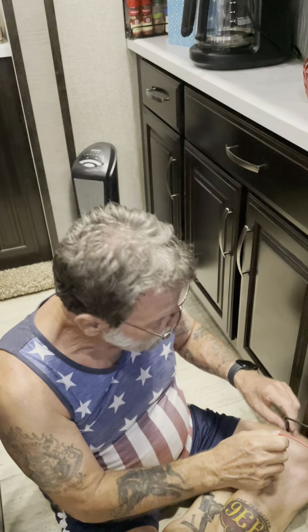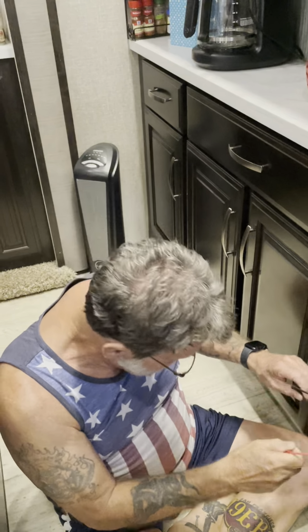If you do have a good pedestal, if you have power at the pedestal, but you don't have power inside the coach, we need to figure out where we're losing power. The next step is we would check our main breakers coming in. If you have a 50 amp coach, you'll have 2 breakers. If you have a 30 amp coach, you'll have a single breaker. If there's power here, then you're losing it somewhere in the circuit breaker panel. If there is no power here, then you're losing it between the pedestal and the main breakers.